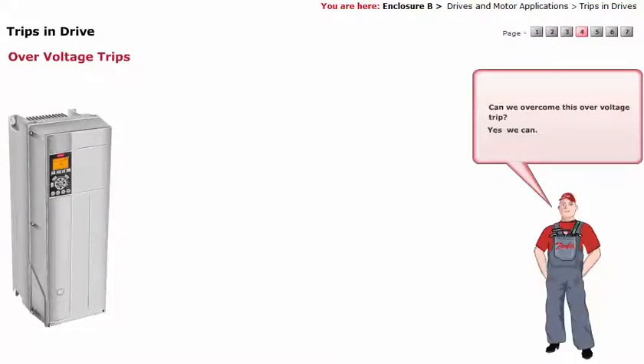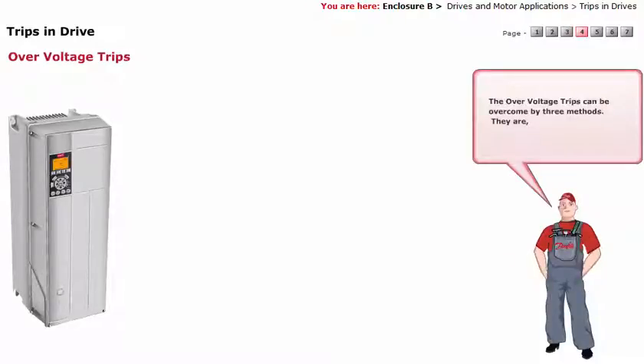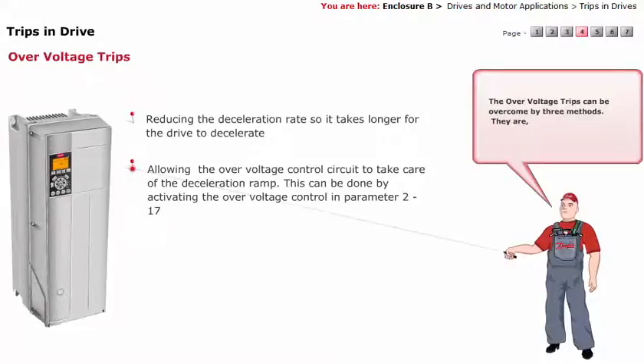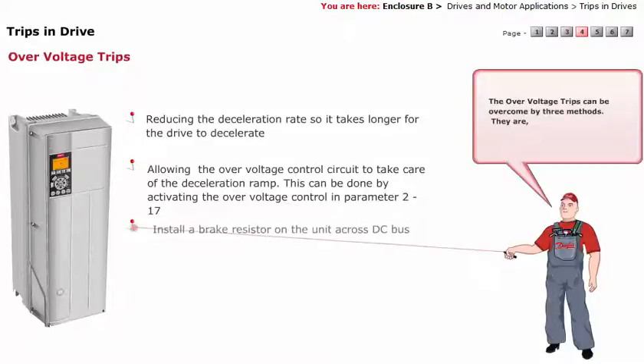Yes, we can. The over voltage trips can be overcome by three methods. They are: reducing the deceleration rate so it takes longer for the drive to decelerate; allowing the over voltage control circuit to take care of the deceleration ramp, which can be done by activating the over voltage control in parameter 217; or installing a brake resistor on the unit across the DC bus.